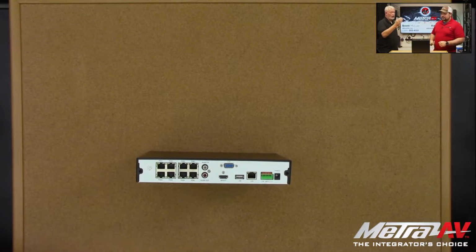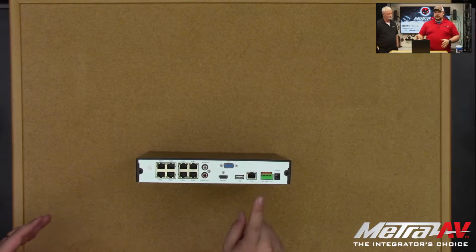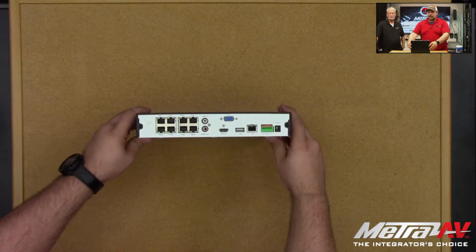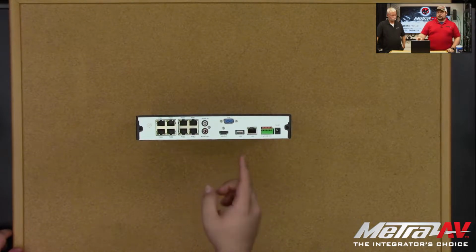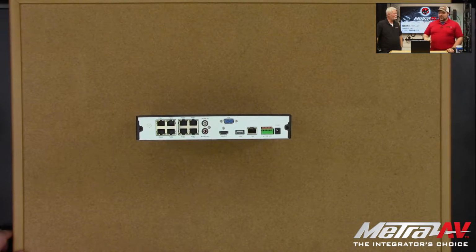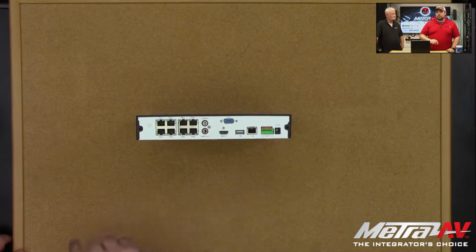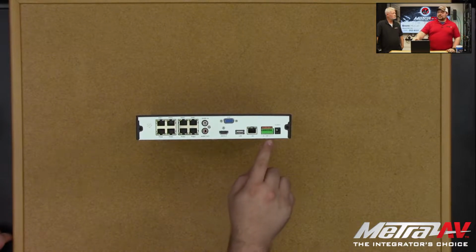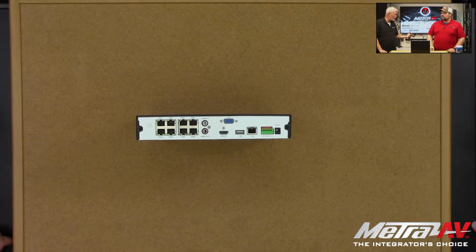So now, what options do we have for automation built into this? On the back of the unit, we have our different I/O inputs and outputs. We have our C for common, and our NO for normally open. Normally open what? Normally open relay. From there, we have our ground connection, which corresponds to our 4, 3, 2, and 1 ports, because that is contact sensing. So this will actually detect another device somewhere else that triggers this. If you have a door contact or a motion detector or PIR, something like that can trigger this.